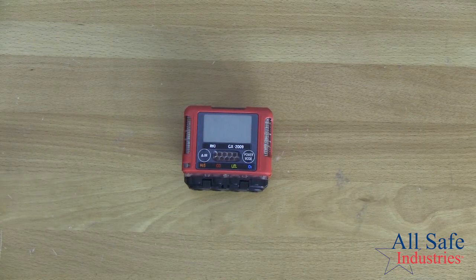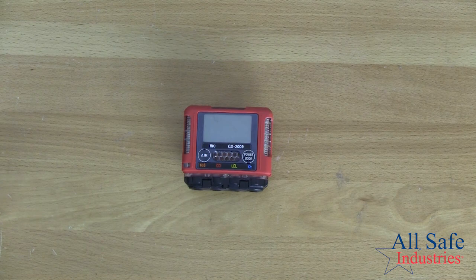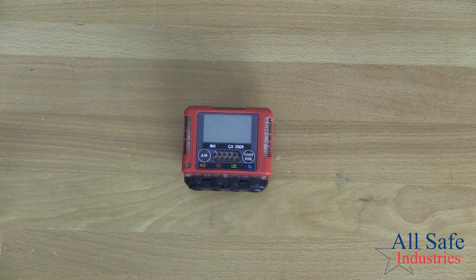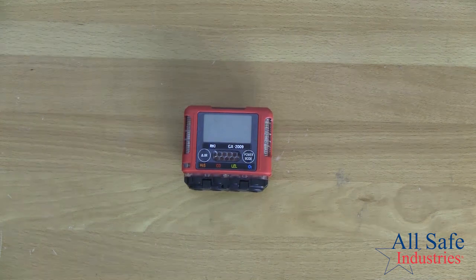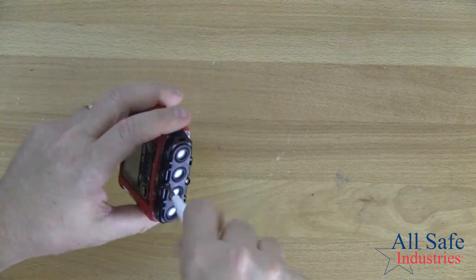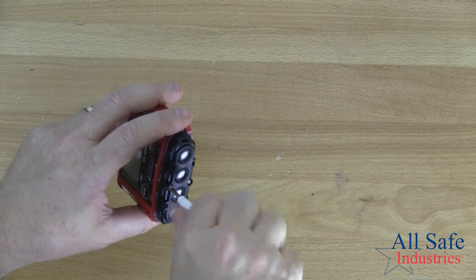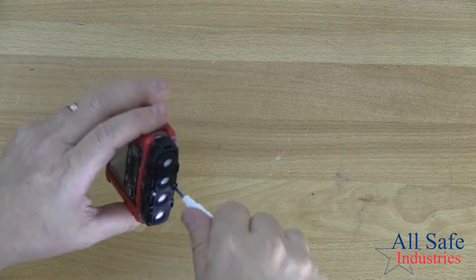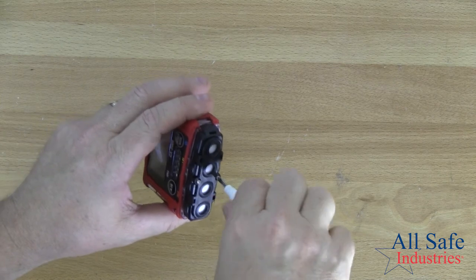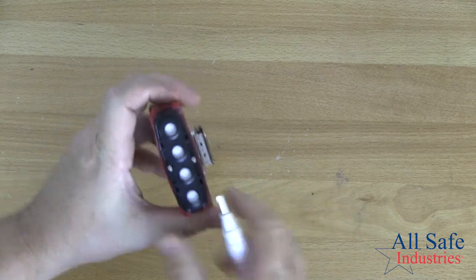There's not a lot of consumable parts, but there are some. There are the 4 different sensors inside the instrument. There are some filters on the sensor retainer, and there's also the 2 rechargeable nickel metal hydride batteries, and so periodically those items might need to be changed. So I'm just going to grab a simple Phillips head screwdriver and loosen the 2 screws on the bottom of the sensor retainer, and I'm just going to keep unscrewing those until they start to click. That tells me that that has released.